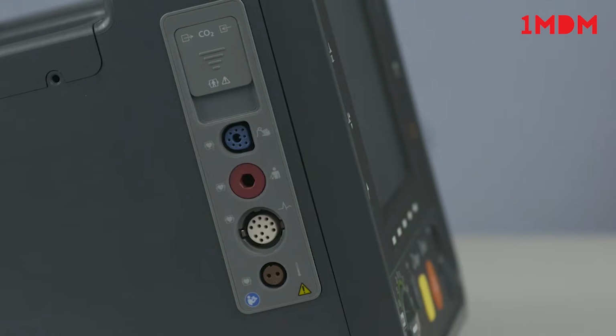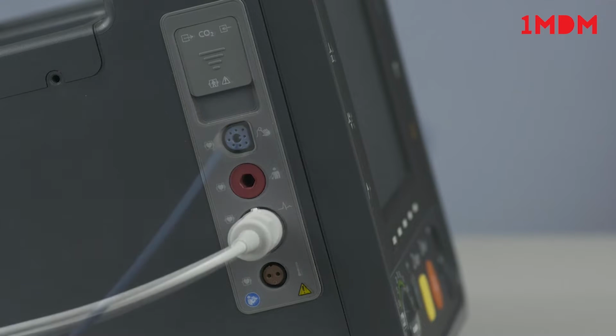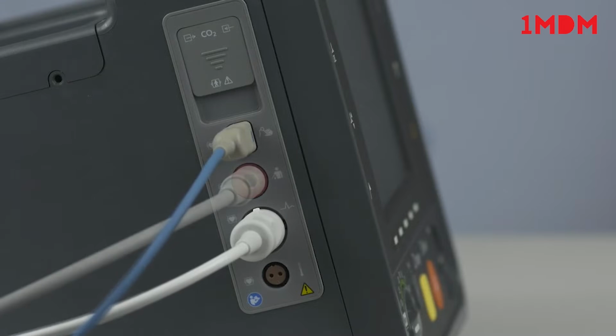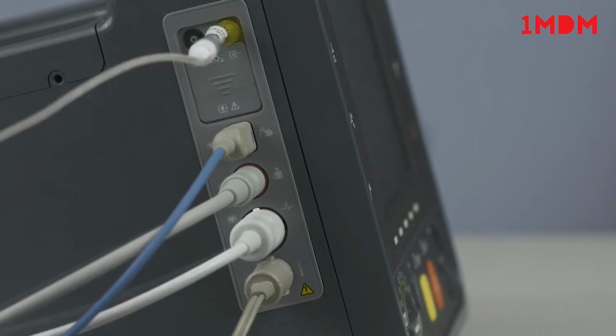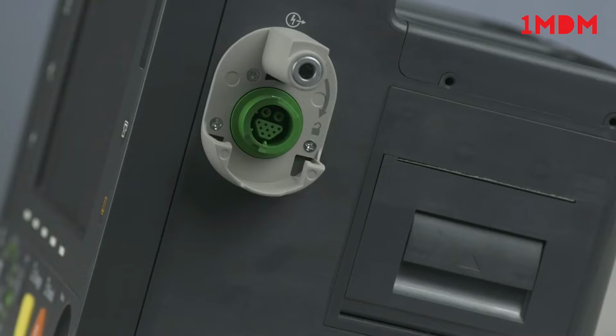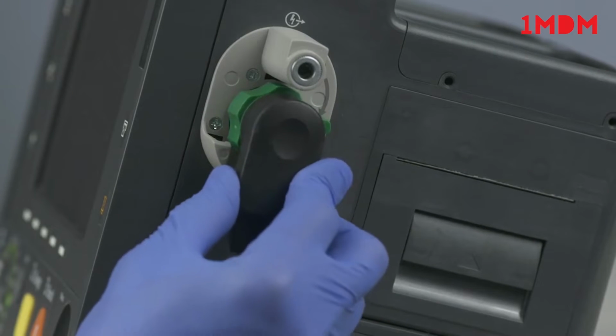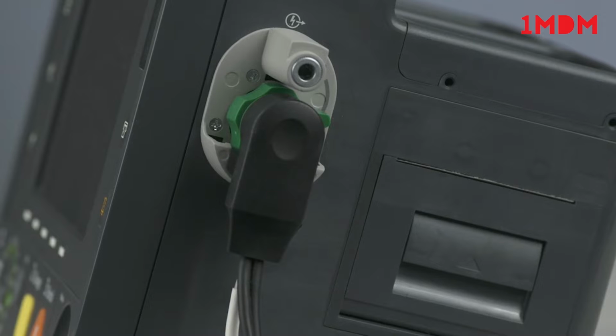Color-coded ports for monitoring cable connections are on the left: ECG, SpO2, non-invasive blood pressure, temperature, and CO2 cables plug in here. A therapy port for paddles, external or internal, or a therapy cable with multifunction electrode pads and, optionally, a Q-CPR cable is on the right side. The printer is located on this side as well.